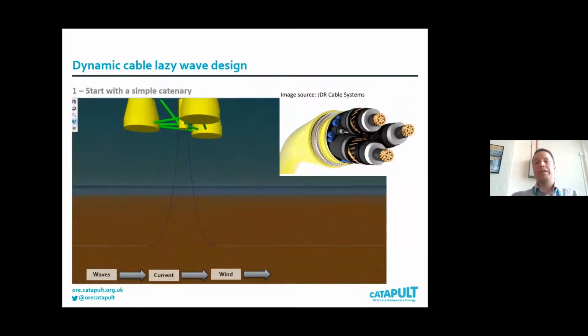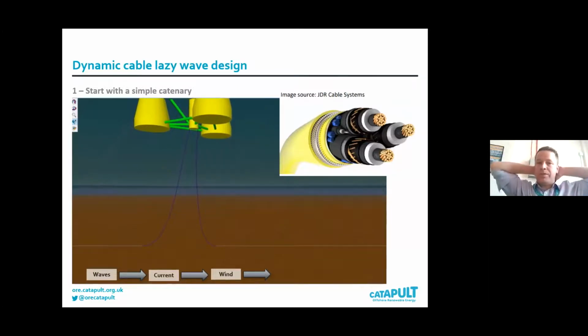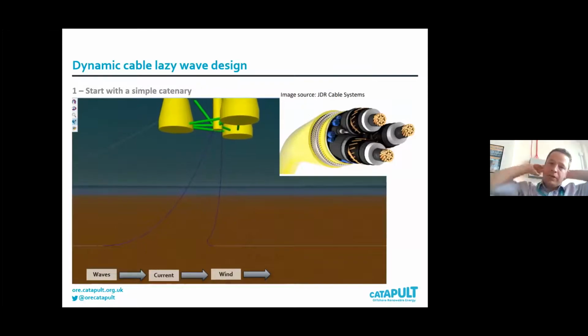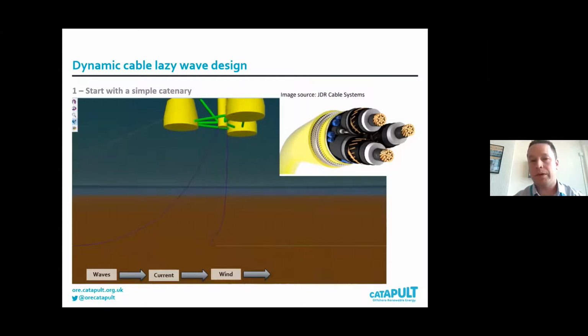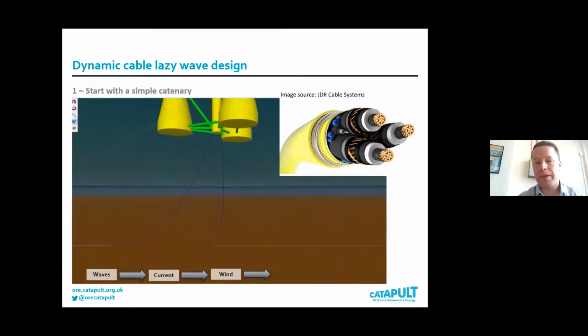So how do we design this? I thought I'd make a nice process for designing this system. So you've got this cable, with all the cores, the armor wire, and so on. When we put this into our global model, unless we're looking at fatigue, typically we can characterize it by basically 3 simple parameters. The outer diameter defines how it behaves when it's contacting the seabed, and also the buoyancy, so that's our first parameter.